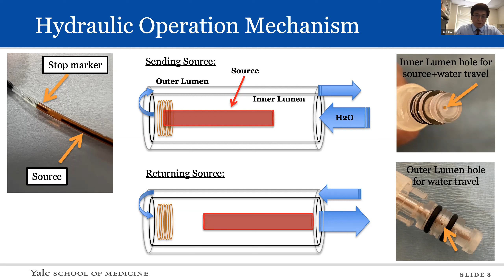After the end of a treatment, the operator flips the fluid control switch, and that makes the syringe connect to the outer lumen. Water is injected into the outer lumen, and once the water reaches the end of the tip, it turns around to the central lumen, passes through the mesh grid structure and pushes the source, and the source comes back to the transfer device. And once the source is back in the transfer device, the operator closes the gate, and the source will be kept in the safe position.